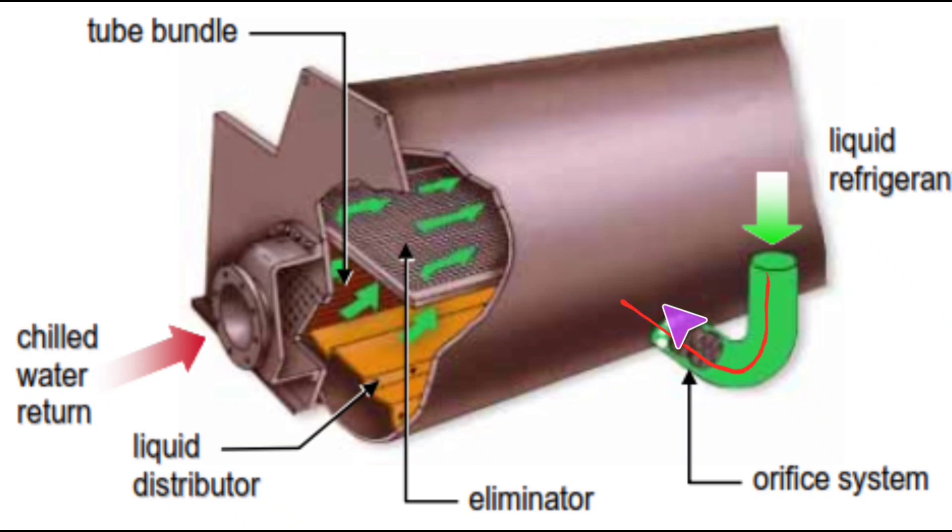So what we're focused on here is as this comes in, say this refrigerant is at a 40 degree saturation and our leaving water coming out of the chiller is at 42 degrees. We would take and do the difference between those, which comes out to two degrees of approach. So it's as simple as that.